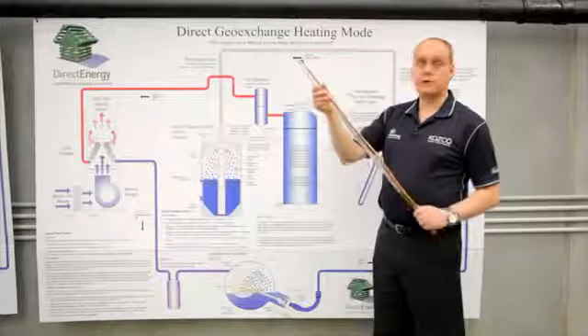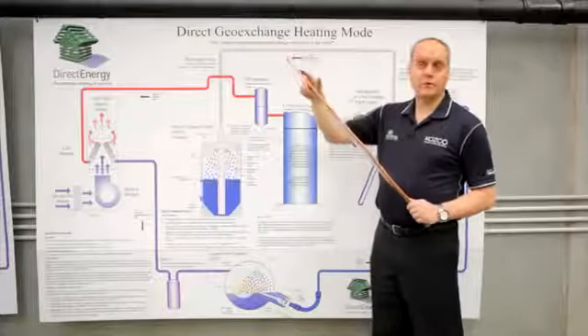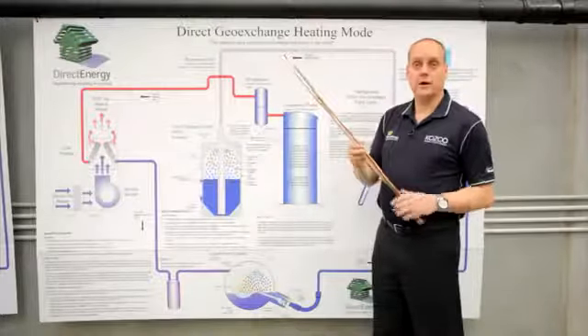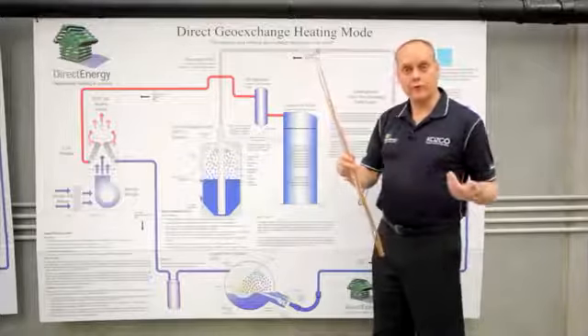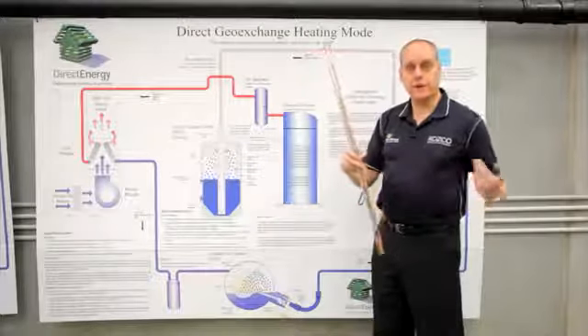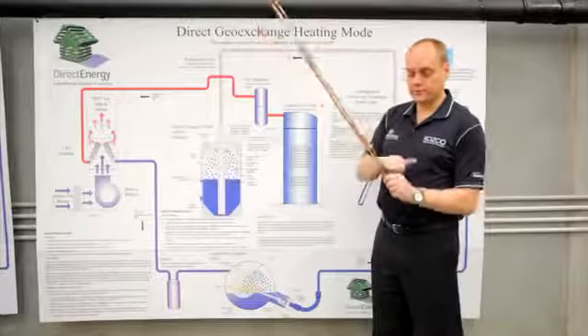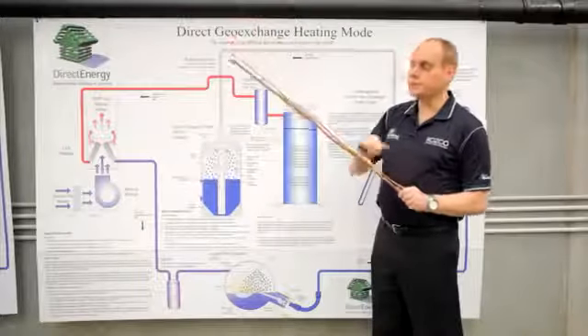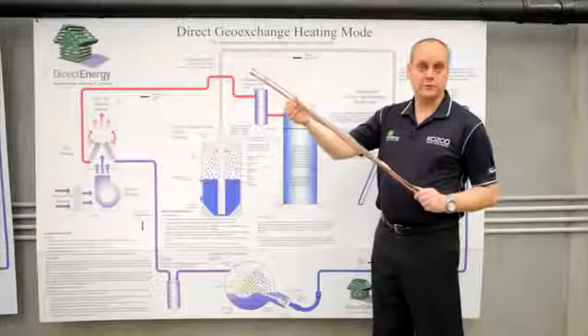Simply reverse cycling the system and putting the 80-85 degree refrigerant down into the ground, and now allowing the ground to draw that heat away from the refrigerant through the copper, through the grout into the ground, allows the refrigerant to be cooled and condensed and come back up the liquid line, forming condensate droplets.